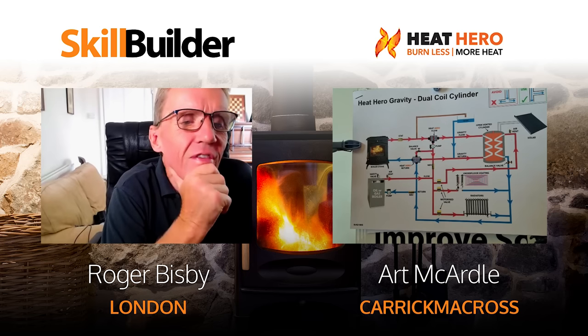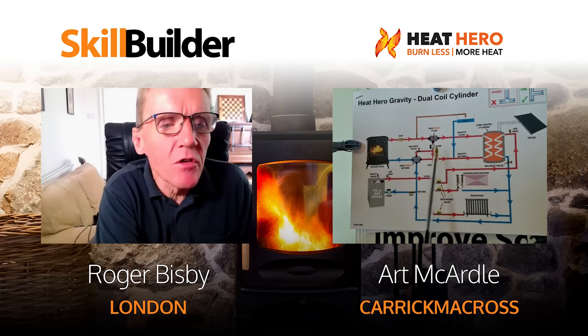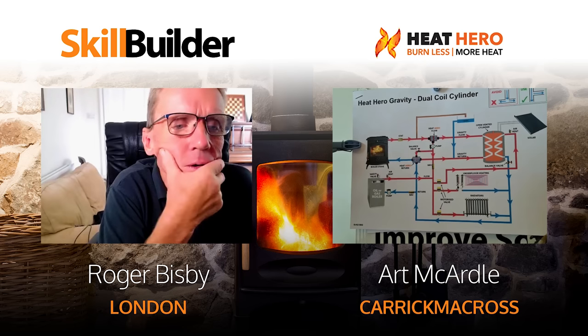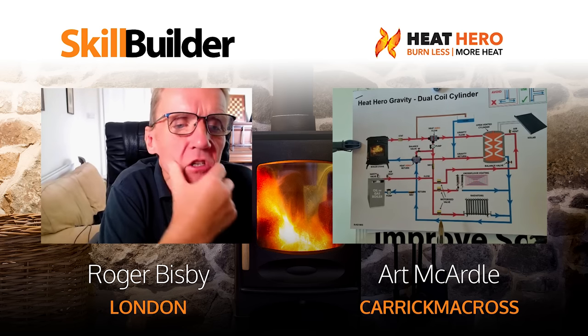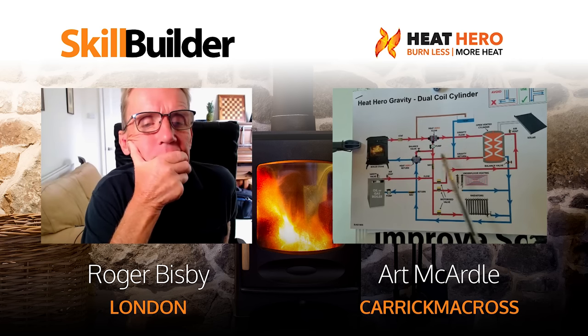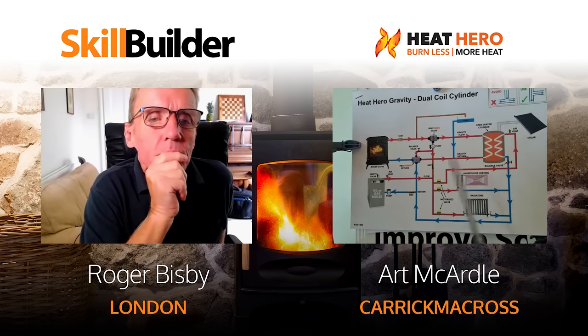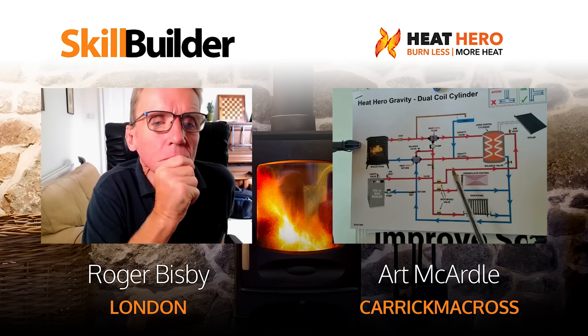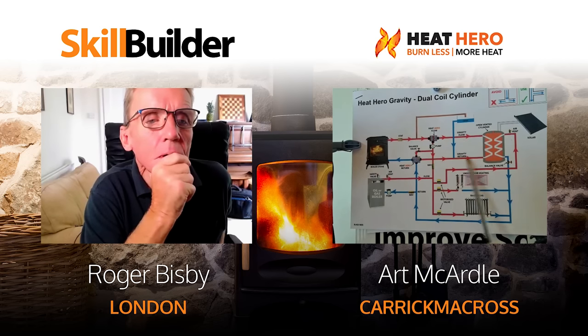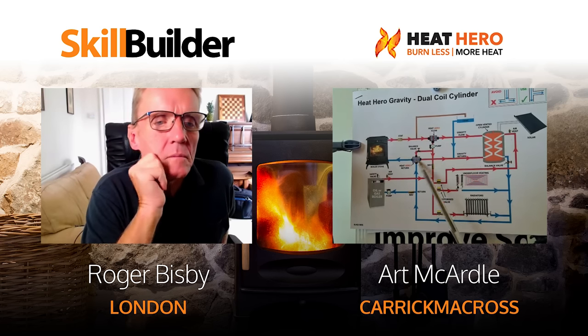The thermostat on the flow on the wood burner - if that drops below temperature it turns off the pump. Then you're relying on the pump on the oil boiler to carry on doing its job. We definitely need a dual coil cylinder here. We don't overly recommend a single coil but we can adapt this to a single coil as well. Not only that - we can zone the radiators, turn off all radiators from the solid fuel boiler and only have it doing hot water, because it's pumped on the circuit. If those zone valves are all off, the pump circulates through the cylinder circuit only.